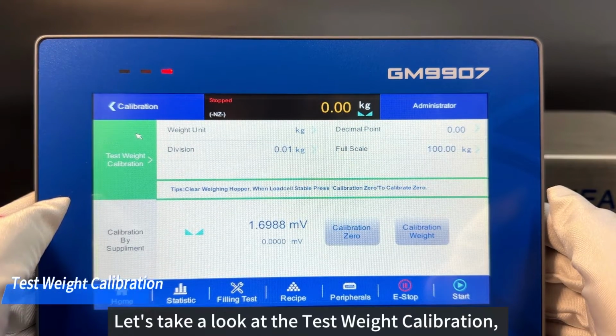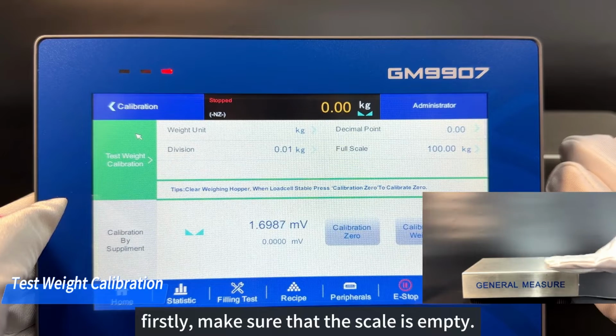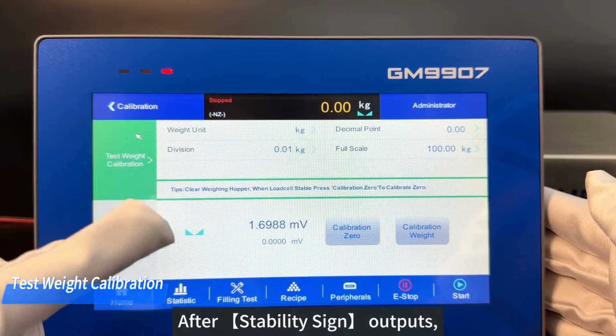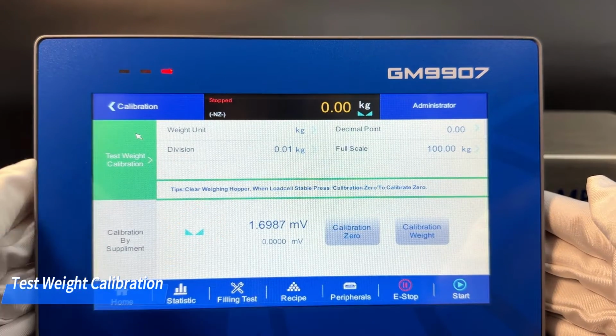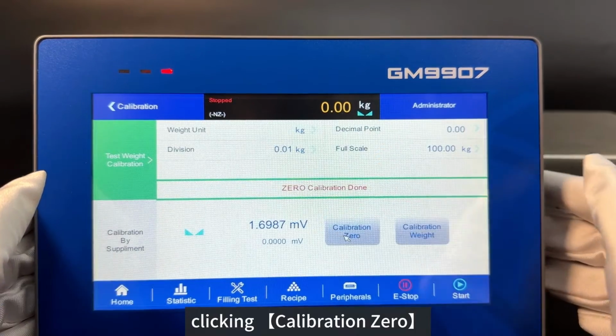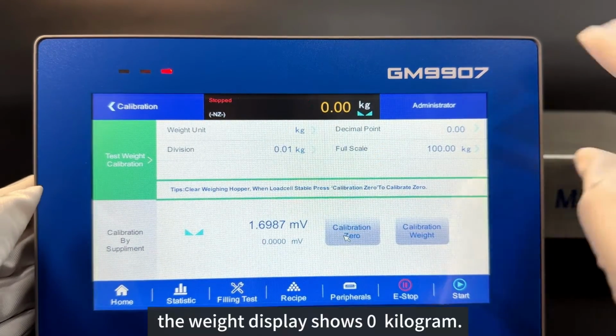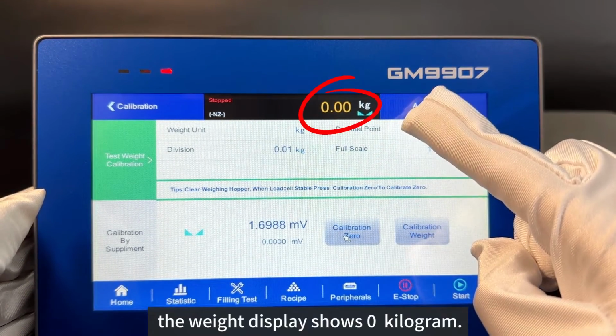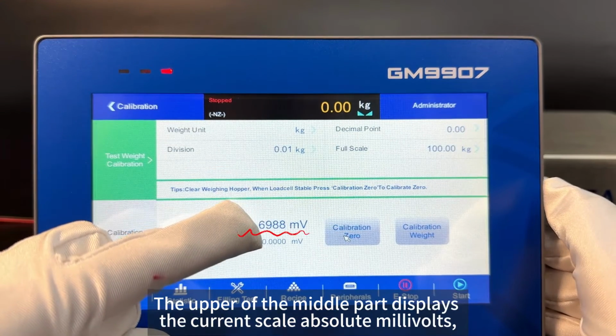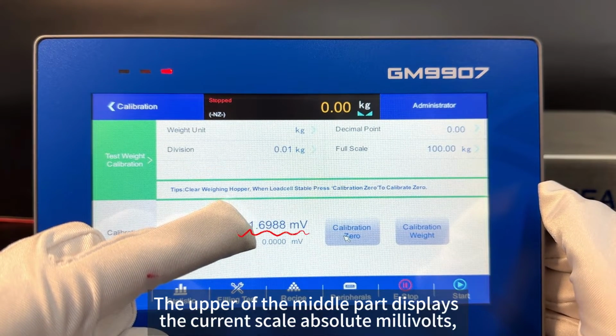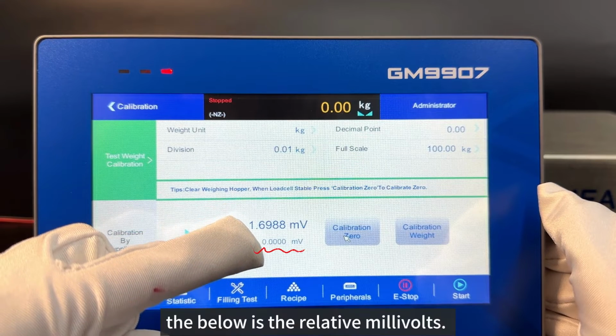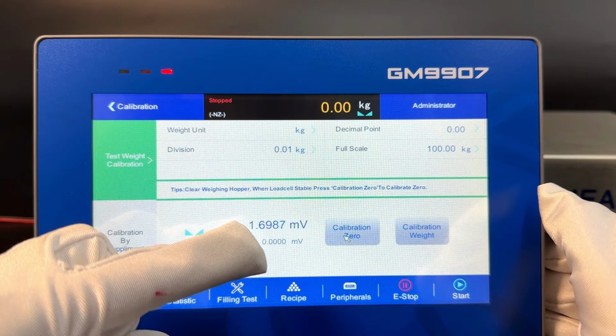Let's take a look at the test weight calibration. Firstly, make sure that the scale is empty. After the stability sign outputs, click calibration 0. The weight display shows 0 kg. The upper part of the middle displays the current scale's absolute millivolts. The one below is the relative millivolts.